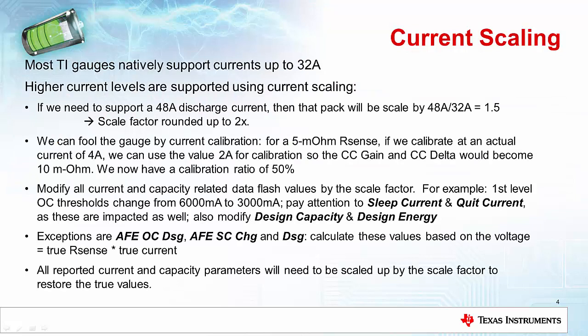So most TI gauges will natively support currents up to 32 amps, but we have a lot of customers that want to use much higher current levels than that. And so for that, you can use current scaling. For example, if you have a maximum discharge current of 48 amps, then based on our maximum of 32 amps, you'd need to scale the pack by at least a factor of 1.5. And so we round that up to about 2 times.